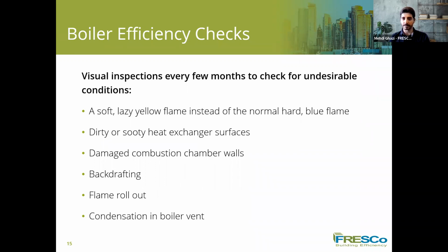This can again be easily addressed by cleaning the burners. We can ask our contractor to check our burners and clean them quite regularly, clean the fire side of the heat exchanger, descale the water side of the heat exchanger, and for atmospheric, or natural draft boilers, we can easily adjust the draft and/or fuel pressure in the manifold. And for forced draft boilers, check and adjust the air and gas flow rates. We need to ensure the combustion air grill is clean, as I mentioned, and the dampers, if installed, are operational and have gaskets in good condition. Cleaning and lubricating the damper actuators, if installed, can help in having a good performing boiler room.